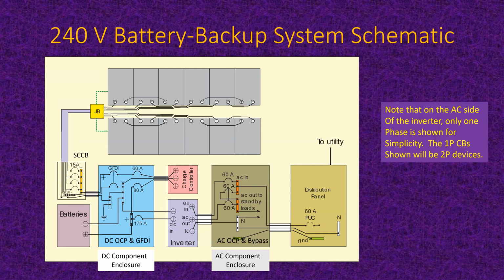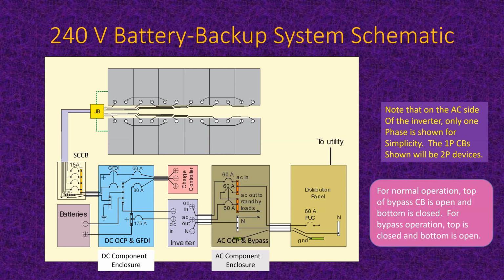So on the AC side here, we're only showing a single phase, but this is in fact a 120/240. So the single pole circuit breakers are actually two pole. In normal operation, the bypass switch is open on top and closed on the bottom, so that you don't go directly from AC in to AC out. You go from AC in to the inverter, let it do its thing, and then to the AC out.